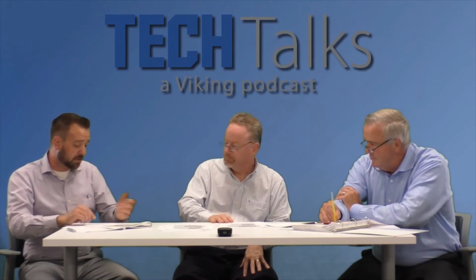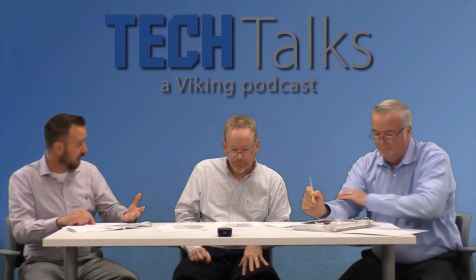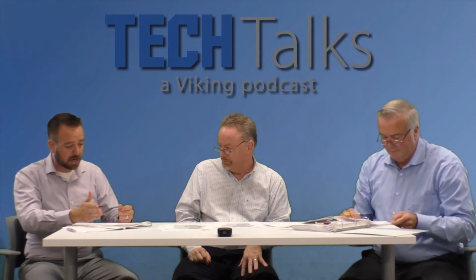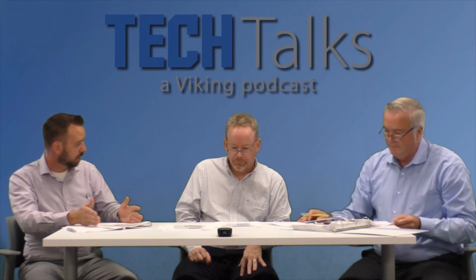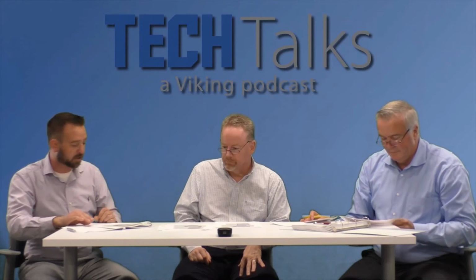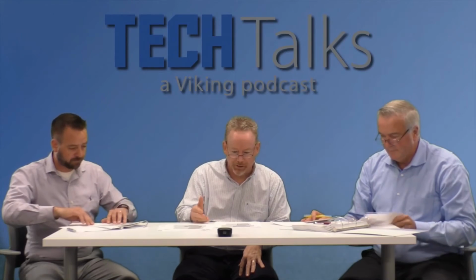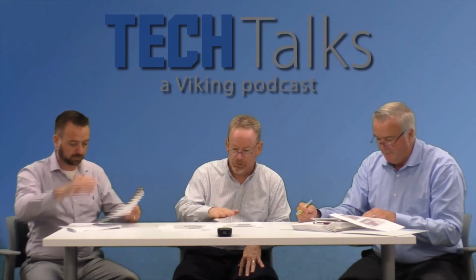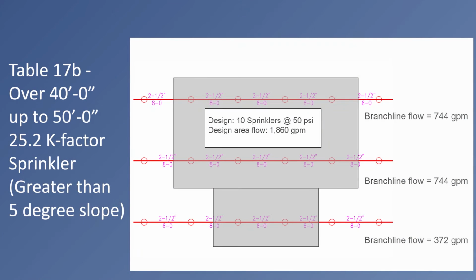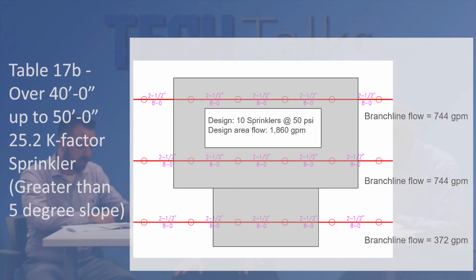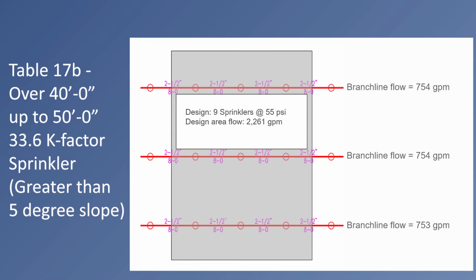Okay. So as you can see, the branch lines shown are 2.5 inch. The mains came out both needing to be 6 inch for the primary and secondary. The same thing occurred, very close again between the K25 at the lower pressure, and the same story with the K33, which didn't change at all because it was a 9 sprinkler design, but it still has a 2,200 gallon flow. Even in that situation, it still has the highest flow out of the 4 K-factors for a 50-foot ceiling.